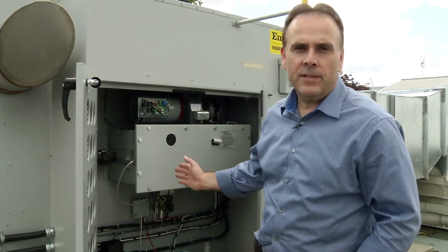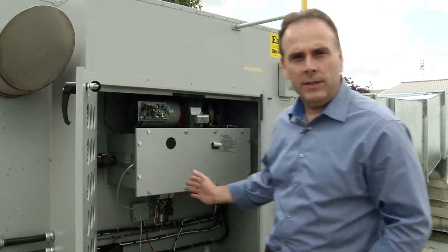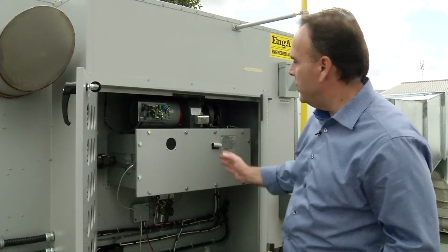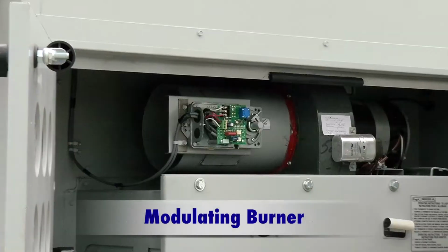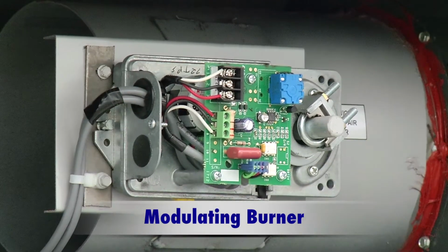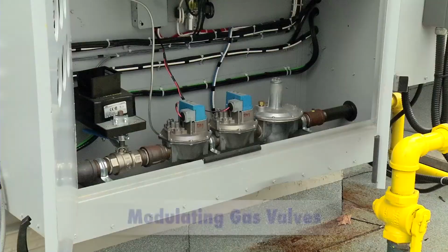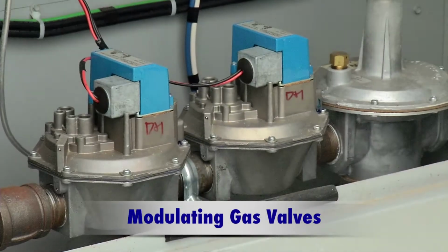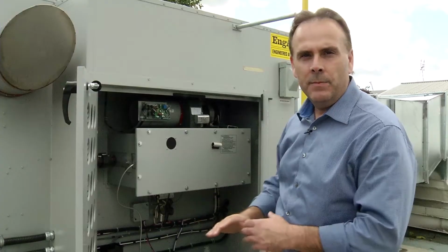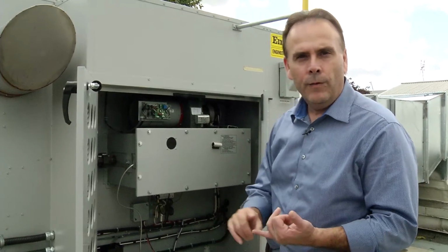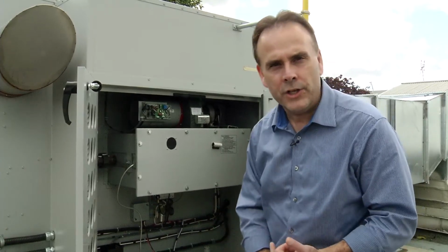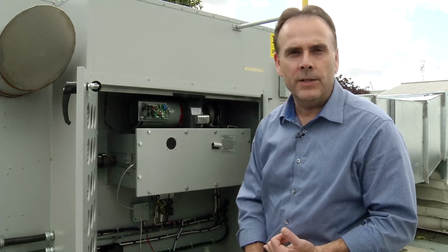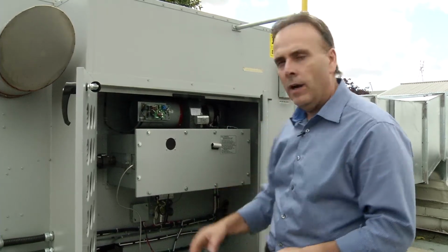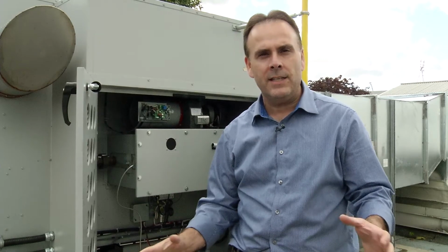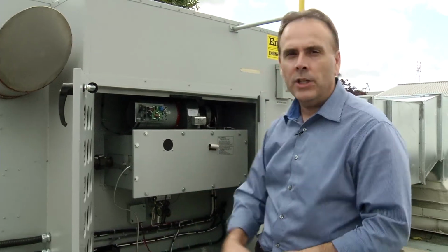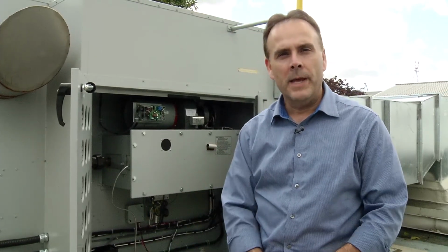Okay, we've opened up the gas-fired section of the makeup air unit to take a look at the gas-fired burner. And what you see is the modulating burner itself, which controls the amount of air going into the combustion chamber, and the modulating gas valves, which automatically adjust for the amount of gas depending on the heat output required for controlling the discharge air temperature and the speed of the supply fan. So this is where the majority of the gas savings are achieved, at the modulating gas burner on the makeup air unit.